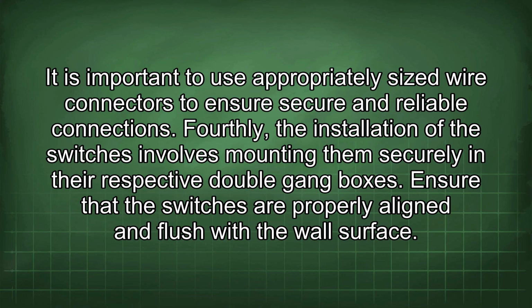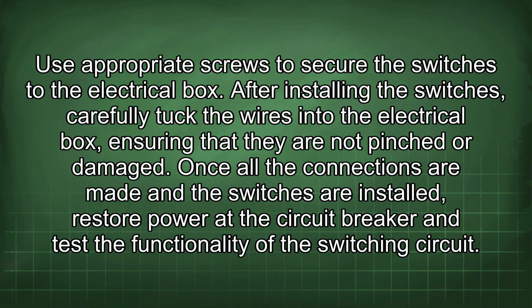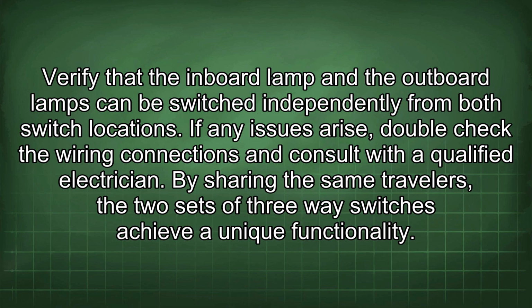Fourthly, the installation of the switches involves mounting them securely in their respective double gang boxes. Ensure that the switches are properly aligned and flush with the wall surface. Use appropriate screws to secure the switches to the electrical box. After installing the switches, carefully tuck the wires into the electrical box, ensuring that they are not pinched or damaged. Once all the connections are made and the switches are installed, restore power at the circuit breaker and test the functionality of the switching circuit. Verify that the inboard lamp and the outboard lamps can be switched independently from both switch locations. If any issues arise, double-check the wiring connections and consult with a qualified electrician.